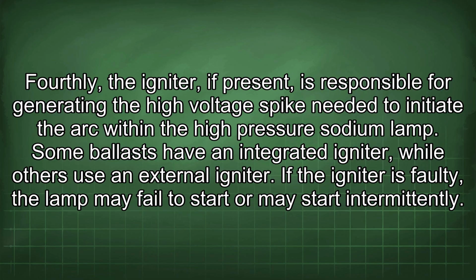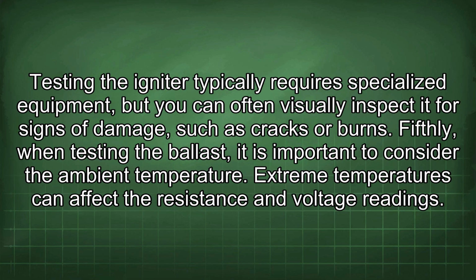Fourthly, the igniter, if present, is responsible for generating the high voltage spike needed to initiate the arc within the high-pressure sodium lamp. Some ballasts have an integrated igniter, while others use an external igniter. If the igniter is faulty, the lamp may fail to start or may start intermittently. Testing the igniter typically requires specialized equipment, but you can often visually inspect it for signs of damage such as cracks or burns. Fifthly, when testing the ballast, it is important to consider the ambient temperature.